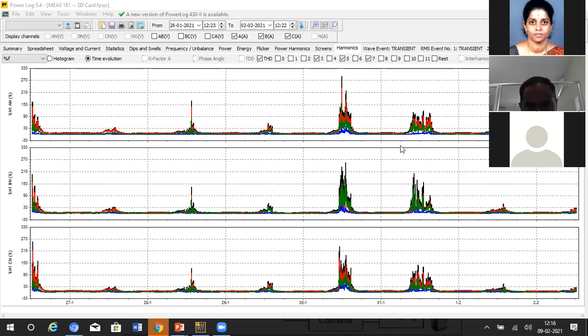The unfortunate part of solar PV generation is that the solar PV plant supplies only a pure sinusoidal current with unity power factor. But most of our loads - LED lamps, lifts, UPS systems - are non-linear loads requiring harmonics and distorted current. My solar PV supplies only pure sinusoidal, in-phase current, meaning it won't supply any reactive power. So the entire active power, even more, comes from the solar PV, and only the distorted power is drawn from the grid.